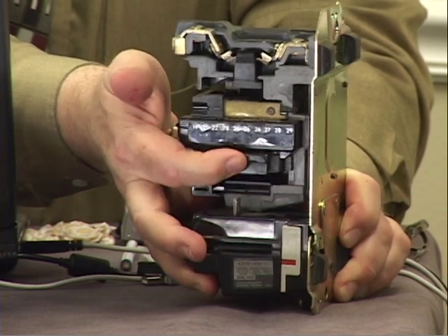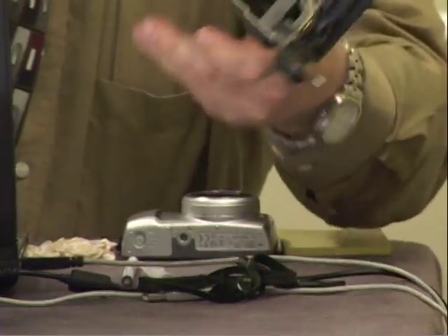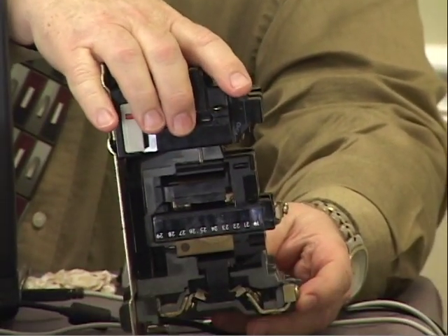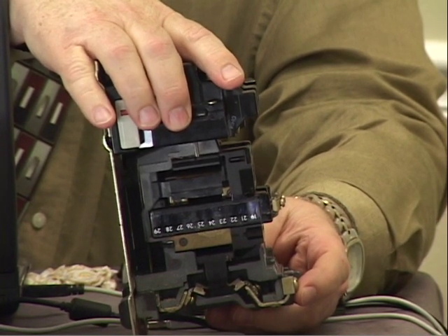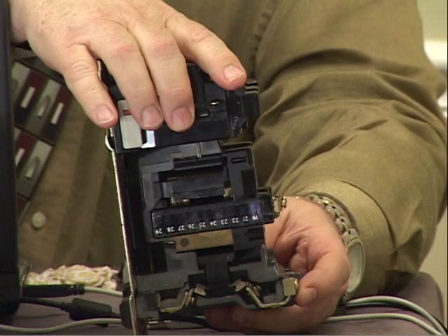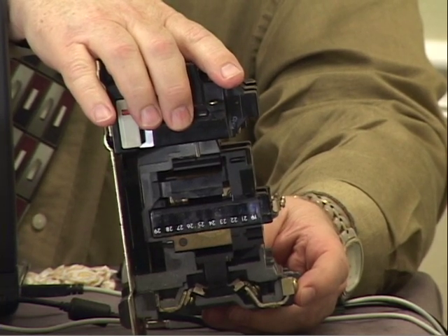It's the same way with this one. So if you turn it and flip it around the other way, what happens if I mounted it upside down somewhere? It's already closed. Exactly, and it's probably not going to be as solidly closed as it should be, so it's actually going to be arcing, and you're going to really burn it up.